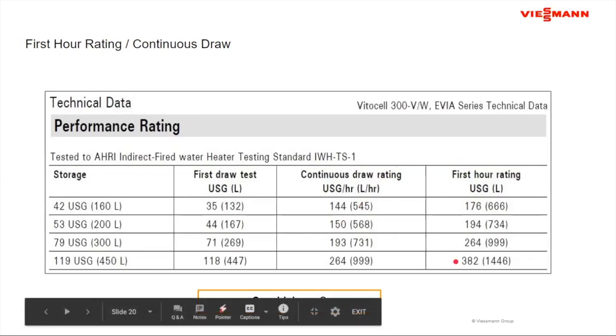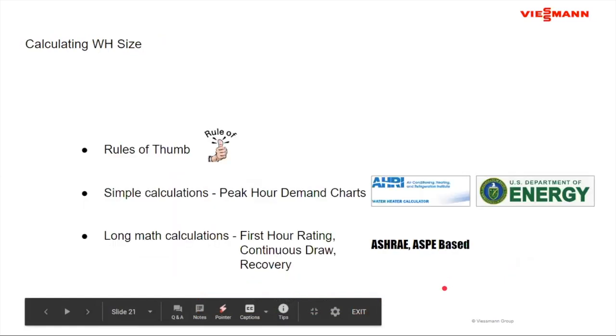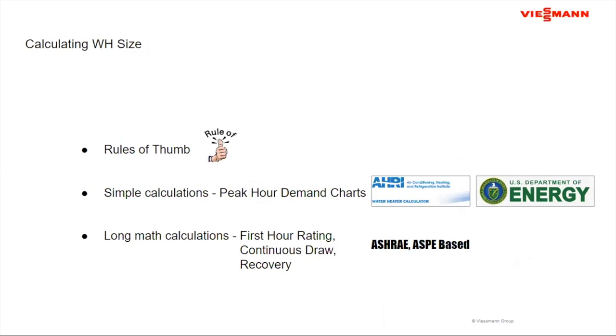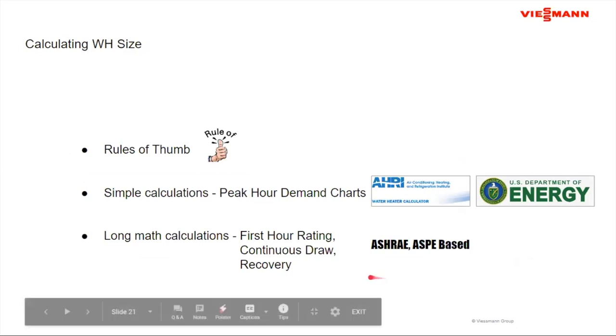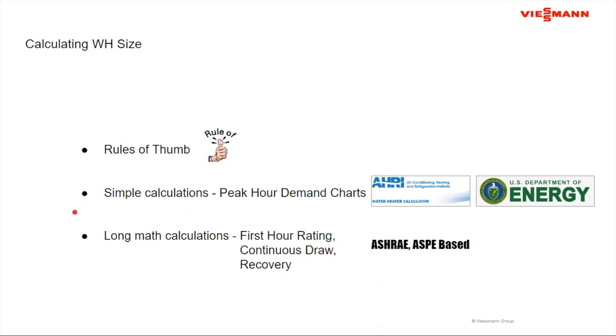So the question then becomes, if this is how it's rated, how do we choose which one? There are a lot of different ways of going about sizing. I'm like everybody, I have a rule of thumb that I use in a pinch to size a water heater, and rules of thumb are usually based on experience. There are simple calculations, and these are peak hour demand charts. We'll look at those. And then there are long math calculations. Yeah, I use all three of them.